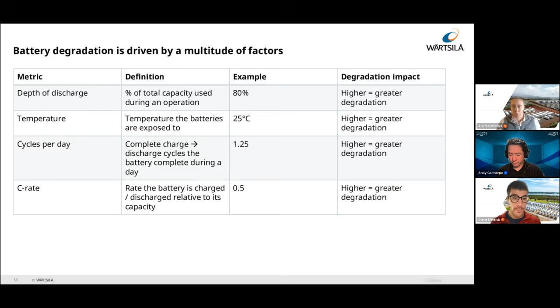One way we're thinking about this is with an application called scenario generation. The idea is to take all the indicators I mentioned—C rate, depth of discharge, cycles per day, temperature—and help asset operators understand how their asset will degrade over the long term. For example, if a battery's been in operation for a couple of years, we measure its operational profile over that time and map out the impact on degradation, then answer questions like: if you keep operating as is, how long will this battery last until end of useful life?